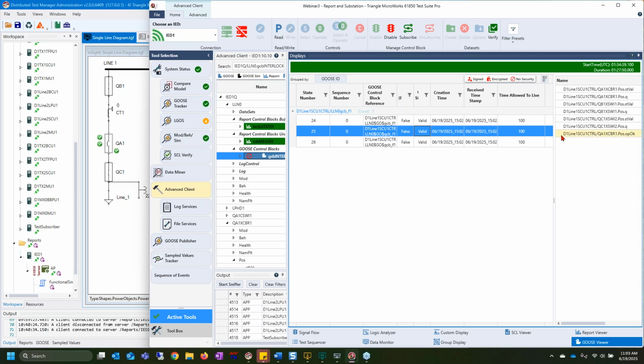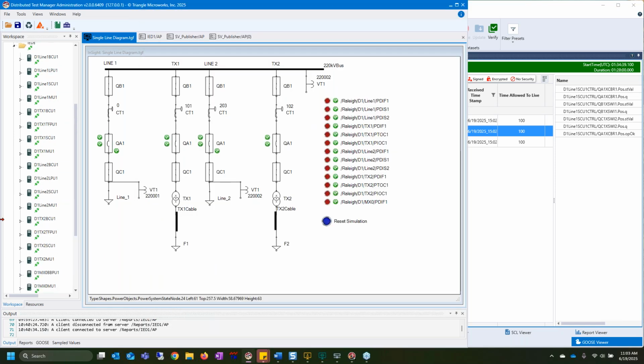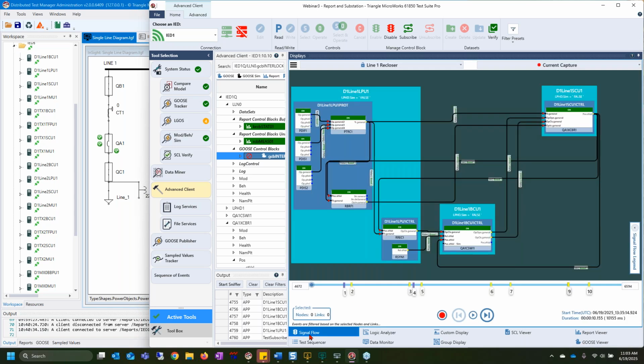We can see what GOOSE streams are out there, and we can get values out of the GOOSE viewer. But in reality, this is not for TSP. The GOOSE is intercommunicating amongst all of my devices here. So how can Test Suite Pro actually monitor the communication between, say, the SCU and the LPU? Well, that is where the signal flow comes in.